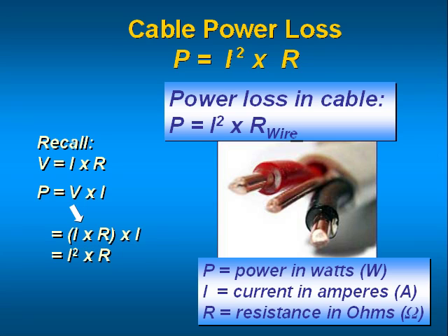Both of these parameters are affected by the diameter and length of the wire cable. The larger the cable, the less its resistance will be. The longer a cable, the greater its resistance will be. In selecting a wire size, you would go to a wire chart and select a wire size that would meet your voltage drop or allotment and be able to handle the current and power loss that is specified.